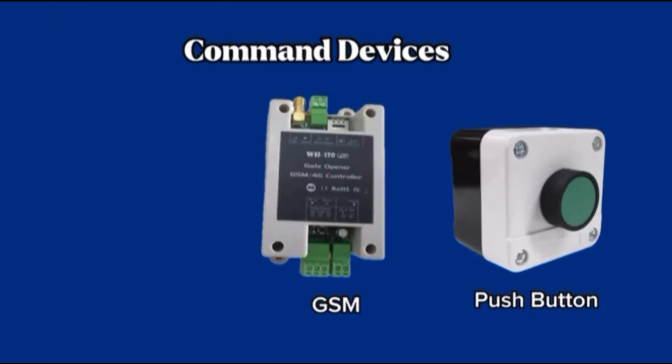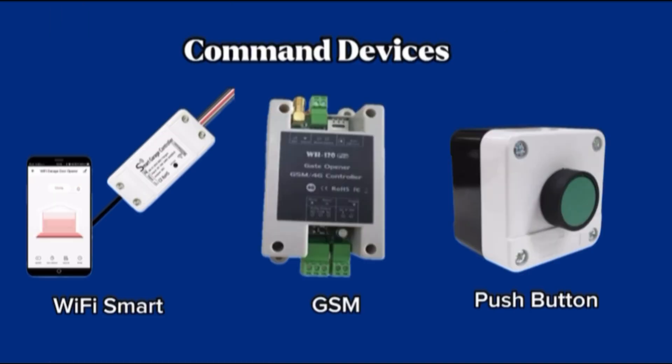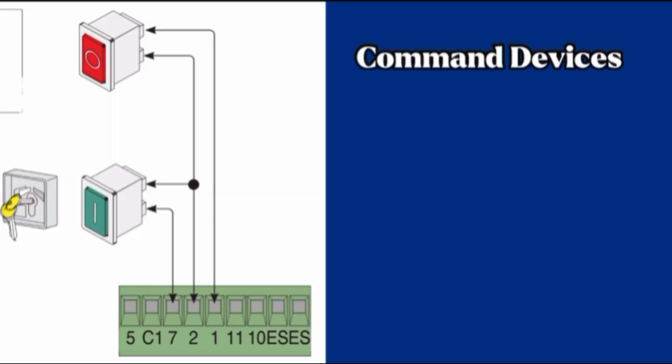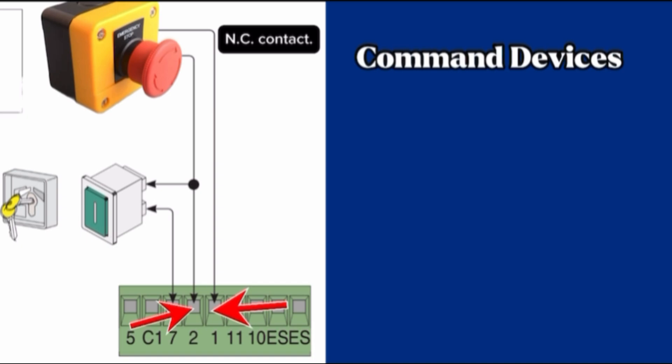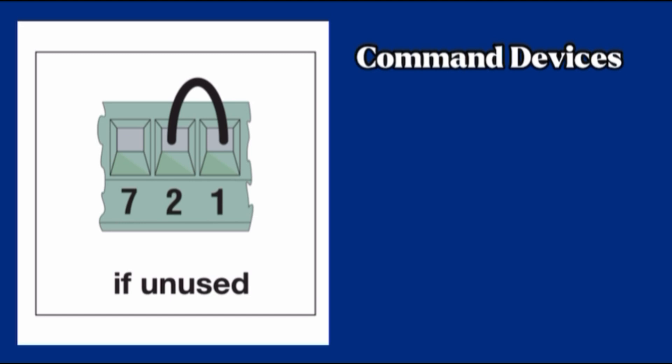Command devices. Terminal 1 with common 2, stop button. It is NC contact. Gate stop button with exclusion of automatic closing. To resume movement press command button or transmitter button. If unused, short circuit contact Terminal 1 and Terminal 2.